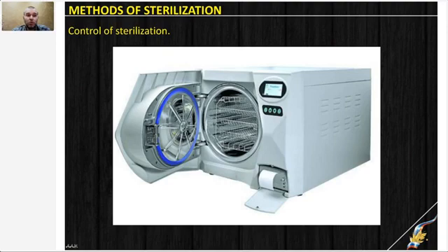And of course, it is a more suitable measure because you can take that printed bill and keep it for any purpose you need. If any check will come, you can open a specific book and you can show in which time period which devices were sterilized. You will show that all procedures were correct, time was correct, and temperature was correct at every time point of the sterilization procedure. Temperature was high enough and you performed everything correctly.